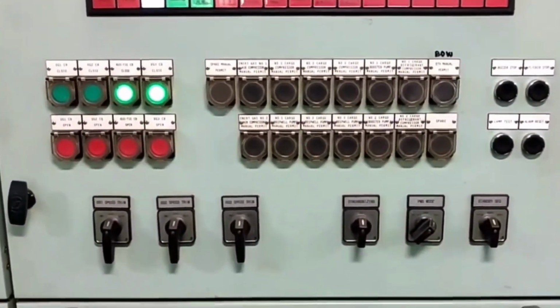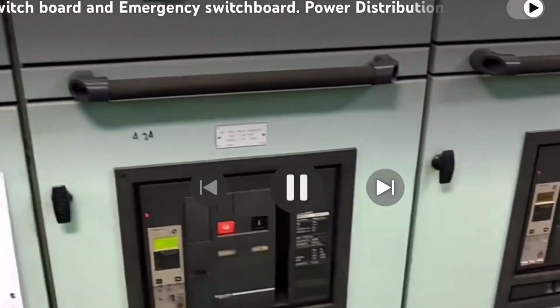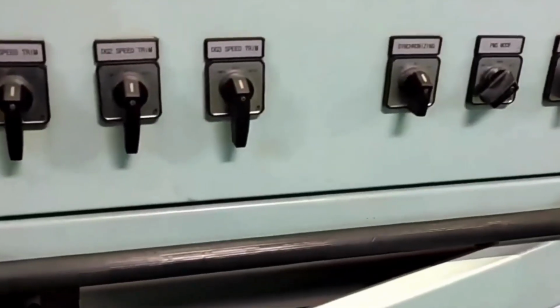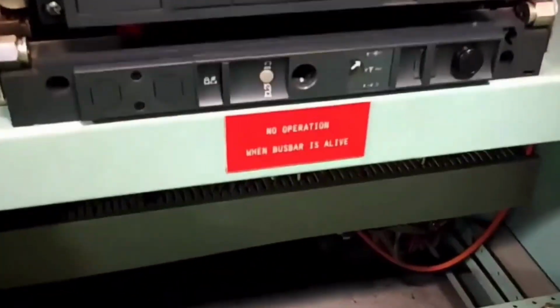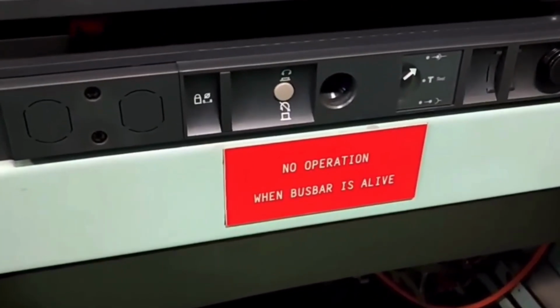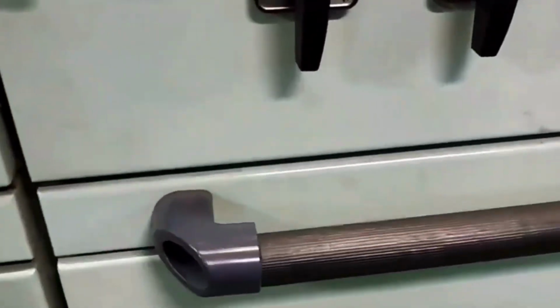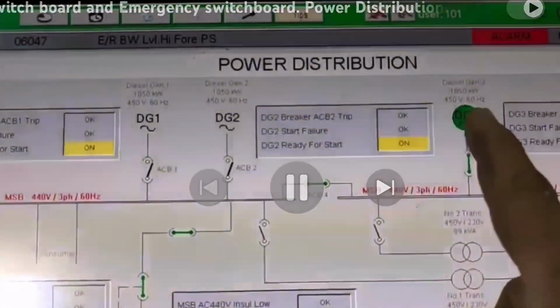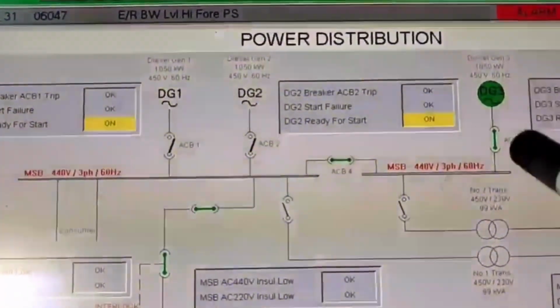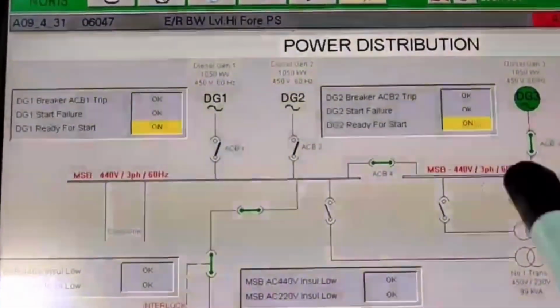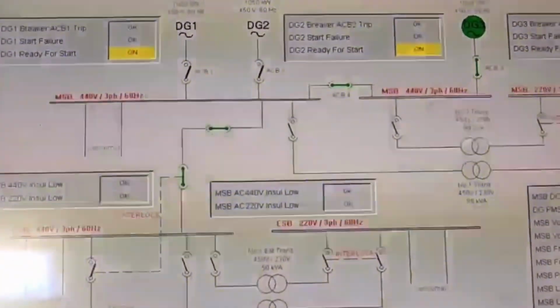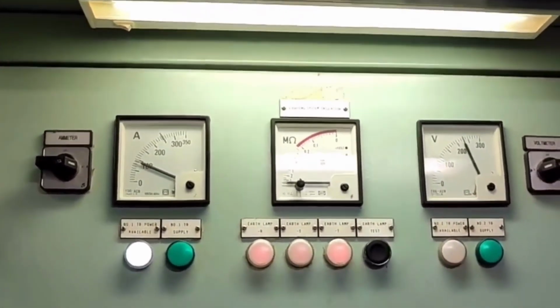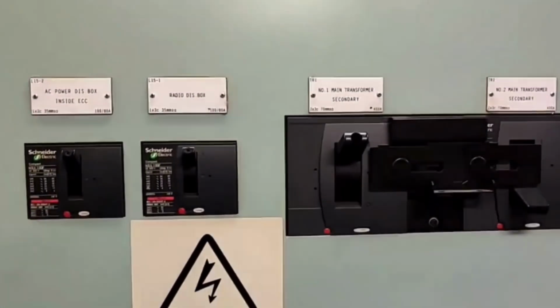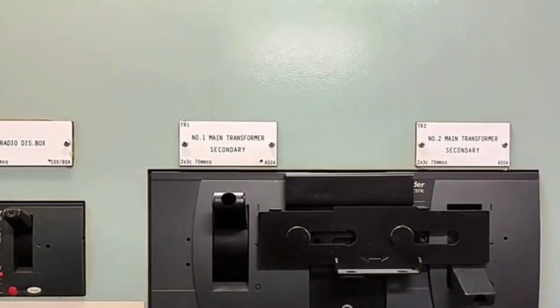Once the power path is established, the system is integrated with the Power Management System, or PMS. The PMS acts as the brain of the ship's electrical network, automatically controlling load sharing, generator synchronization, and start-stop sequences of multiple generators. Communication cables and control interfaces are connected between the alternator control panel and the PMS, enabling real-time monitoring and automation. Engineers then perform functional checks, verifying signals such as voltage, current, frequency, and load feedback are accurately transmitted and displayed. Synchronization tests are carried out to ensure the alternator can smoothly connect to the live bus without causing disturbances. With all systems properly connected and tested, the alternator becomes a fully integrated part of the vessel's power network, ready to deliver reliable and controlled electrical power across all operations.